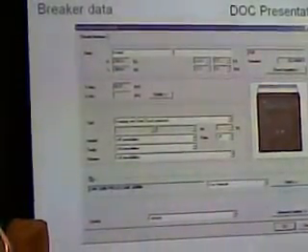and the breaker data. Breaker data, I think since you are an ABB channel partner, you are familiar with breaker sizes and types and everything. So we can go directly here to select. If you select this button, it goes to the library, and from the library you can choose ACB, MCCB, MCB, switch disconnector, all the ranges are there. So from that you can pick up. So automatically it comes over here.